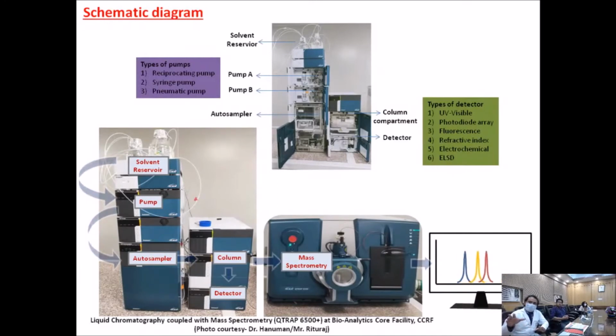It is pumping and pushing the solvent through the auto sampler towards the column compartment, followed by the detector. This is coupled with a mass spectrometer. When we combine the HPLC with the mass spectrometer, as sir has already explained in earlier sessions, it enlarges the applications of HPLC. At that time, HPLC acts as a feeder, not as a detector, because we are not going to use the detector of the HPLC.